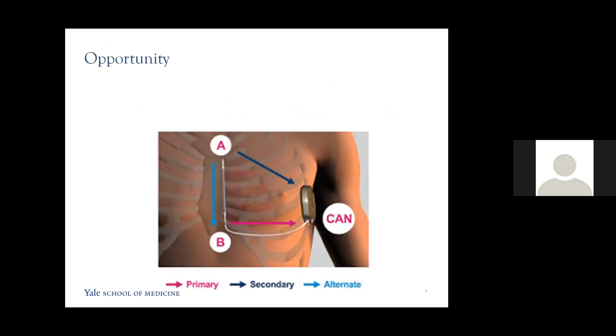So let's talk about the opportunity here for improving care. So non-transvenous ICDs, and the Boston Scientific device is what I've got shown right here. As I mentioned, uses far field signals that are derived from one of 3 extracardiac electrode pairs. In the subcutaneous ICD, the electrodes are located in the can at the proximal aspect of the parasternal coil, demarcated by B, and then the third electrode is at the tip of the parasternal coil, marked with A. And any combination of these vectors can be used for sensing.